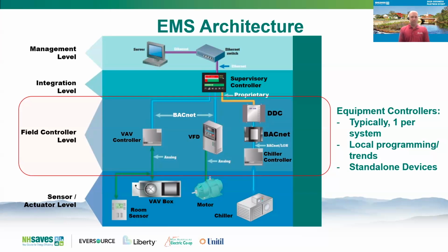And those controllers at the field level can operate standalone. You can disconnect them from the two levels above, and they will operate just fine. Now, sometimes when that happens, schedules will get overridden or default to 24/7. Some of the energy efficiency sequences will not occur because those are driven from the integration level. But generally speaking, the brains of the system is at the field and equipment controller level. That's where a lot of the programming exists and control of the equipment.